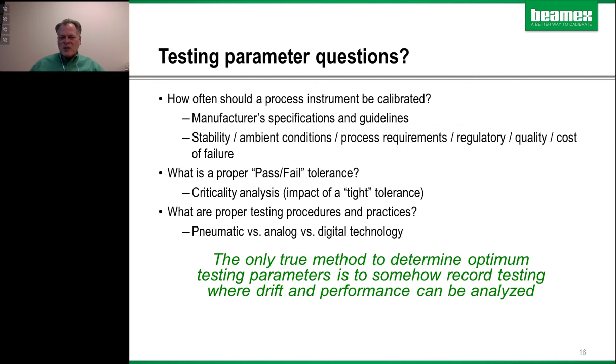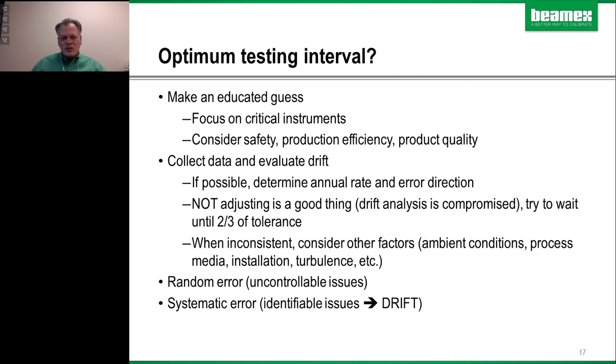And then, what are your best practices within, not just at your plant, but within your organization? How do you check a DP flow meter? There's got to be the best way, and maybe it's not what somebody like Beamex would say, or some consultant. It's like, what is the best way for your organization and at your plant? And know that things are getting better and better with today's digital instruments. They're performing much, much better than the old pneumatic days. But what I say is the only true method to determine the optimum testing parameter is you somehow have to collect some data and do some analysis and see how much your stuff is drifting, and then you can make some good judgments. So documentation, to me, is the only way to get a handle on this information.